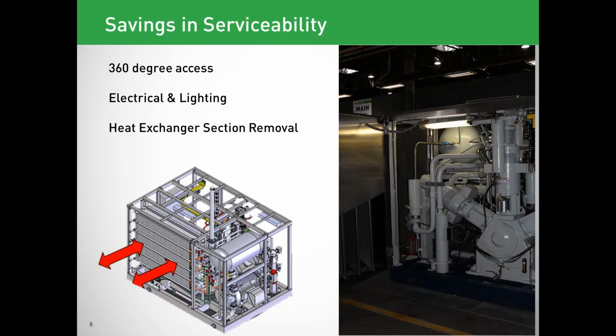hinged on the outsides. This allows the operator to easily inspect the heat exchangers for fouling and slide out a single heat exchanger from the side of the package in case of heat exchanger failure or replacement required. The connections are also easily undone with flange connections, and the whole heat exchanger can be removed very easily without requiring a heavy crane to access the heat exchanger from the top of the package.